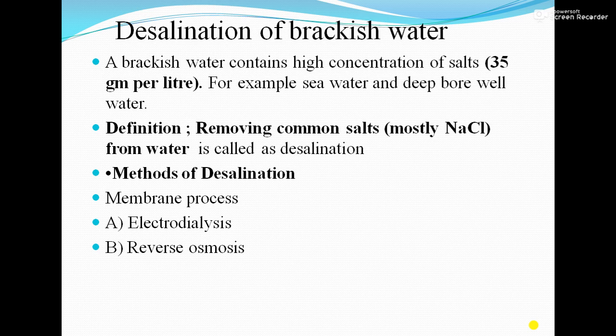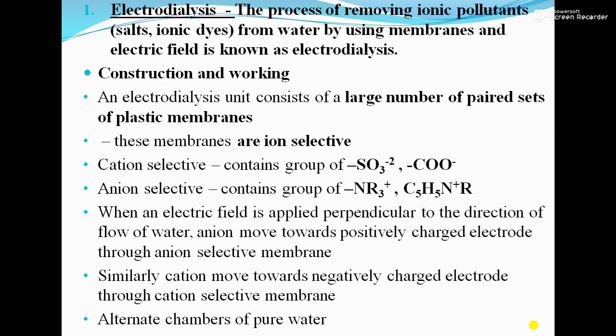Electrodialysis: the word 'electro' indicates there is a cathode, an anode, an electrolyte, and an electric current. Electrodialysis is the process of removing ionic pollutants such as salts and dyes from water by using membranes and an electric field. An electrodialysis unit consists of a large number of paired sets of plastic membranes. These membranes are ion-selective — a cation-selective membrane has functional groups SO₃²⁻ or COO⁻, while an anion-selective membrane has groups NR₃⁺ or C₅H₅N⁺R.